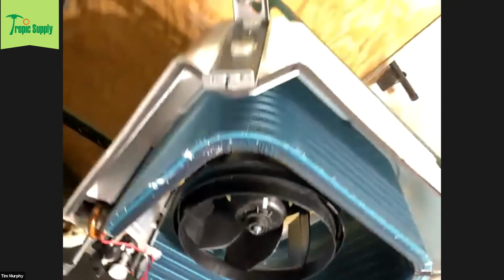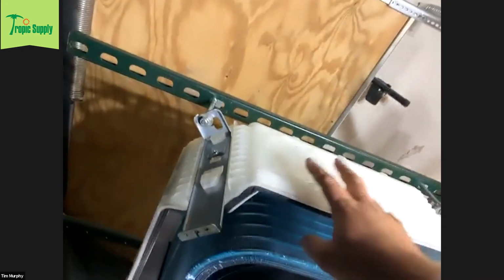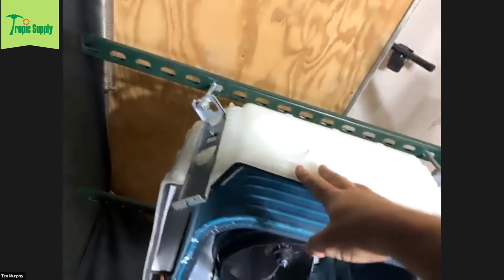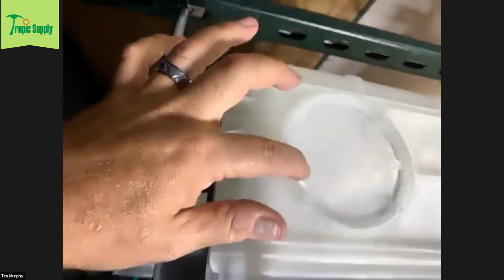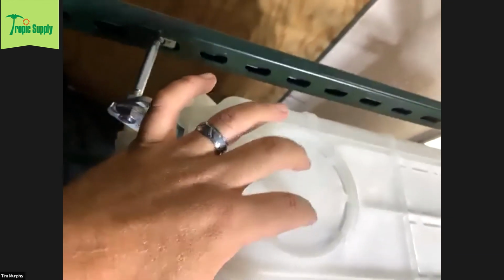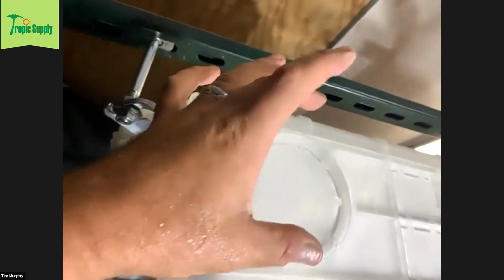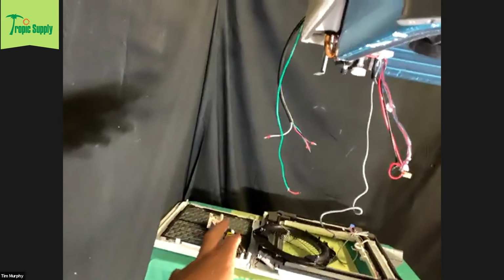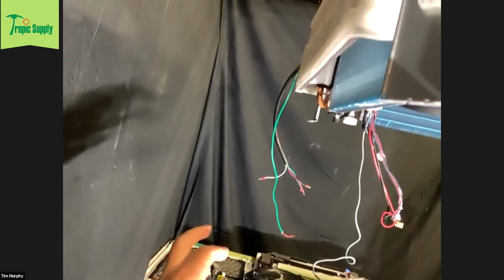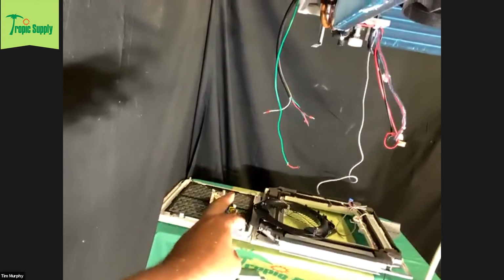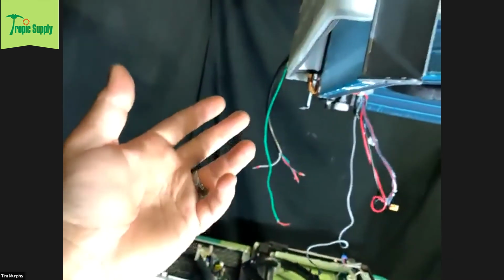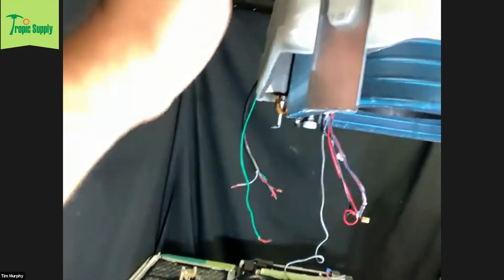One more thing I want to point out: if you're putting this system in a commercial application, you are required to bring in makeup air, fresh air. This is where you're going to tap in your makeup air. But important to note, this doesn't pull the air in, so anytime you need to supply makeup air to the system, you're going to have to add a booster fan. There are hookups and instructions we can provide on how to power or control the booster fan from the unit itself, so it turns on the booster fan when needed and not just running constantly. That's something we can help you with as well.